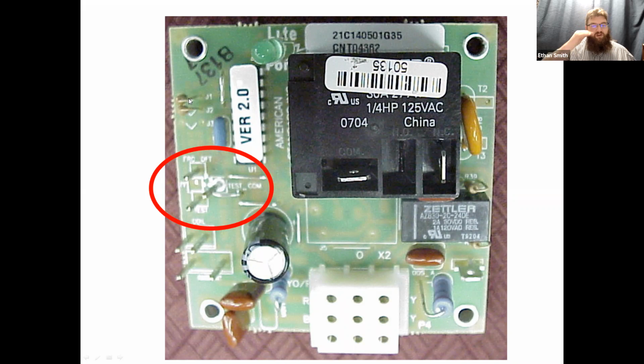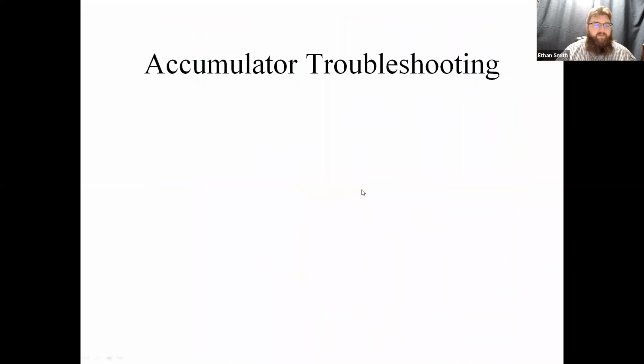So most coils will terminate at 47 degrees. They know that coil's well above the freezing point, should be clear of ice. Depending on your defrost board, you may be able to change that from 47 to 57 or even 70 degrees on your termination. So if you're accumulating excessive frost, let's see what your termination temperature is if you're in that high humidity environment. Okay.